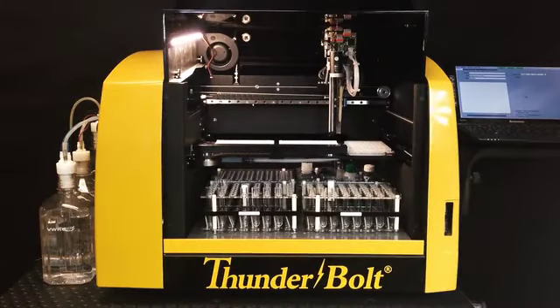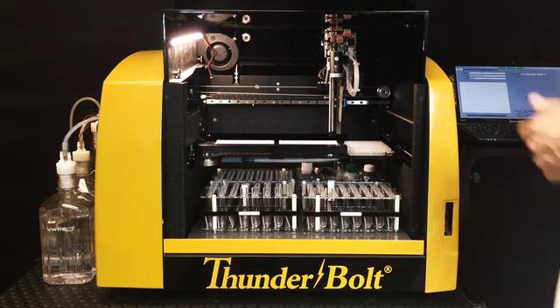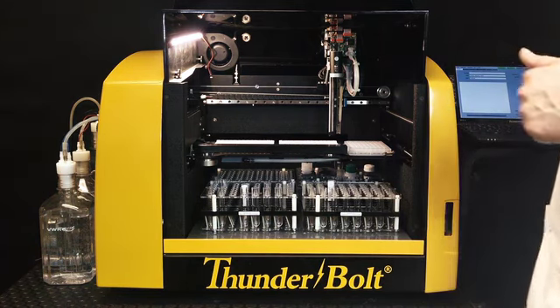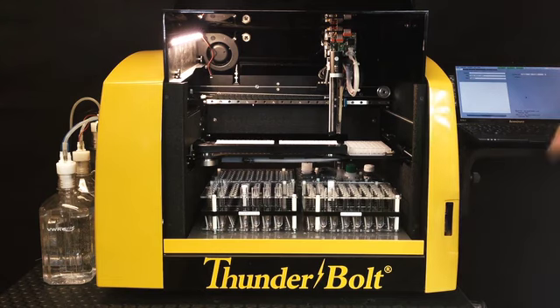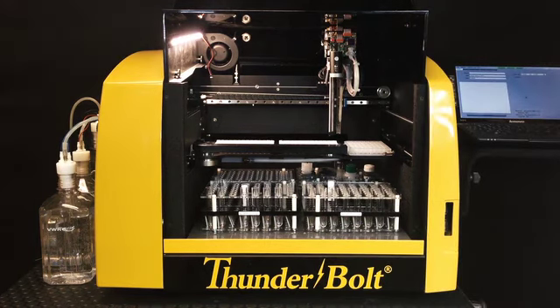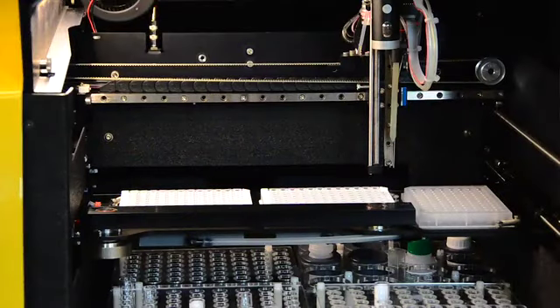Many tests can be run on the Thunderbolt at the same time. It all depends on how many calibrators and controls and samples you have to fit within the two-plate space. There are a few limitations for tests being able to be run together, and that is simply incubation times, incubation temperatures, and a maximum of 2 different wash buffers. We have a location for 2 wash buffers on the side, and we have a pinch valve that allows us to switch between those wash buffers.